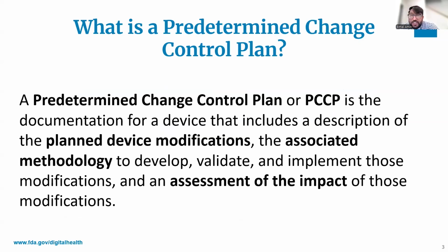So let's start with the fundamental question. What is a predetermined change control plan? At its core, a PCCP is the documentation that a manufacturer submits to FDA describing three things: the specific modifications they plan to make to their device over time, the methodology they will use to develop, validate, and implement those modifications safely, and an assessment of the impact those modifications will have.